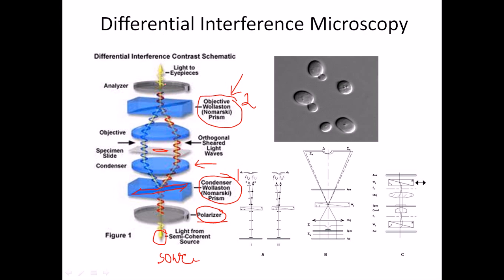The analyzer is used because we placed a polarizer in the previous step. According to the principle of polarization microscopy, if you place a polarizer with a slit in one orientation, you must have an analyzer oriented perpendicularly to cut off extra rays. The analyzer here cuts out rays oscillating in the polarizer's particular orientation and selects light beams with different oscillation directions.